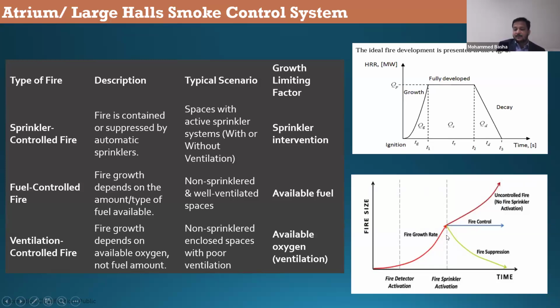But what happens when you have a sprinkler system? The fire starts to get controlled by the sprinklers here. Then it will decay because of the cooling effect of the sprinklers. It is not because the fuel is completed. It is not because there is no oxygen available. It is because of the sprinkler which is controlling the fire. This is called a sprinkler controlled fire. And the top curve is called a fuel controlled fire. Here, what is the governing factor? The fuel. So we call this fire a fuel controlled fire, and we call this fire a sprinkler controlled fire.